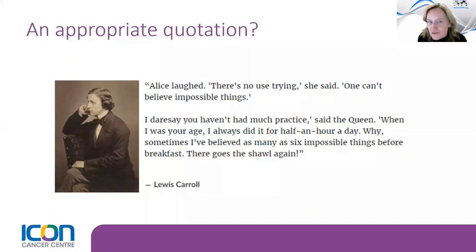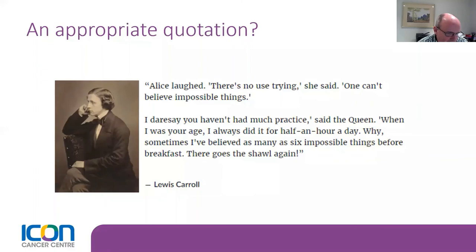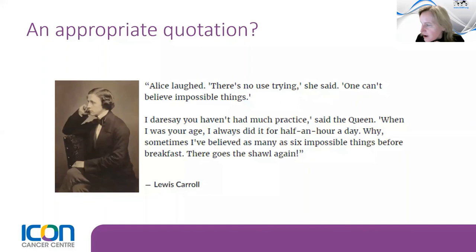For departments or countries without access to an organisation like ACDS in Australia for independent audit: IROC out of the US will do an independent audit, but their SRS audit is only a single lesion — much more well established than the ACDS one, but only a single lesion, so you have to adapt it to test off-axis scenarios. The IAEA can also do independent audits for SRS.